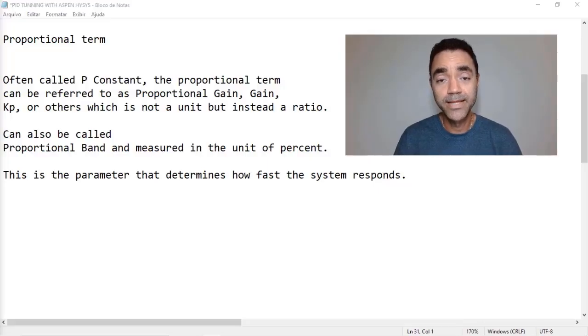It is the proportional band that determines how fast is the response of your system. I usually tell my students that the Kp, that is the proportional band, represents how big is the opening for a control valve each time that it opens. So if you are doing your control and your Kp is big, when your valve opens, it will open too much.